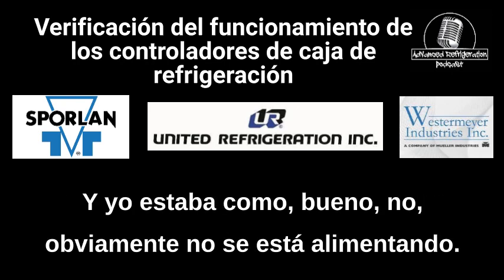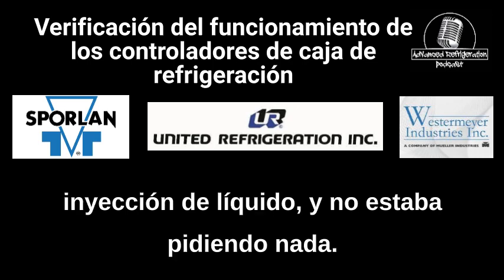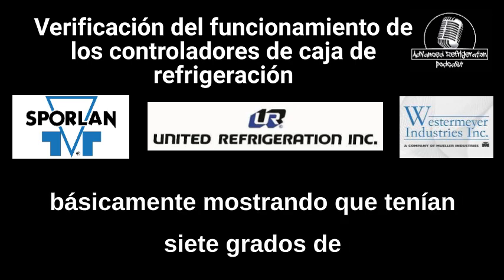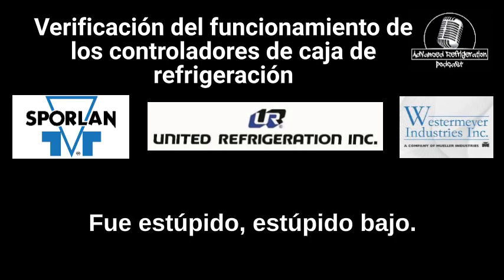And I was like, well, no, it's obviously not feeding. I found the program that was feeding the liquid injection and it wasn't calling for anything. The suction line superheat was so low, probably because of this issue with the pressure transducers, showing that they had 7 degrees of superheat, but in all reality, they did not have 7 degrees of superheat. It was stupid, stupid low.